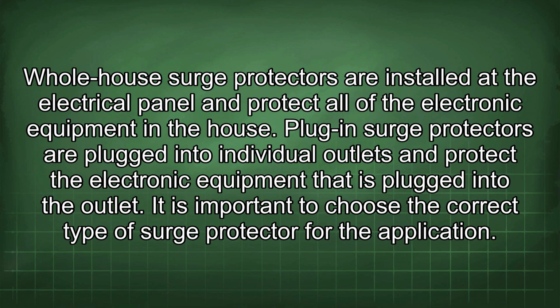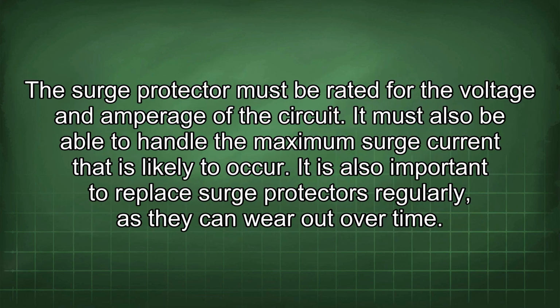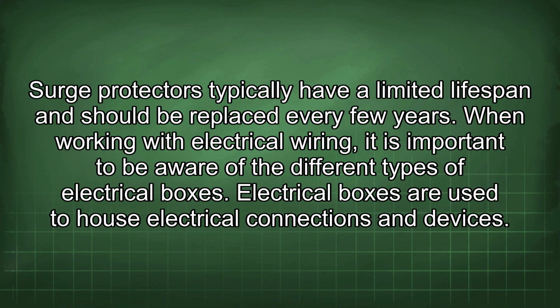It is important to choose the correct type of surge protector for the application. The surge protector must be rated for the voltage and amperage of the circuit. It must also be able to handle the maximum surge current that is likely to occur. It is also important to replace surge protectors regularly, as they can wear out over time. Surge protectors typically have a limited lifespan and should be replaced every few years.